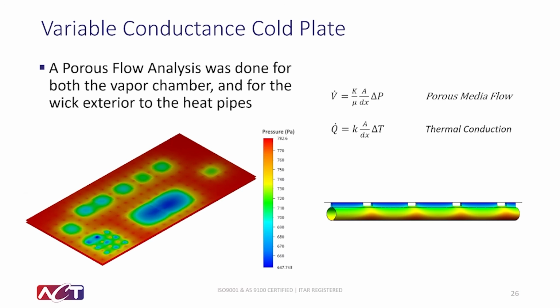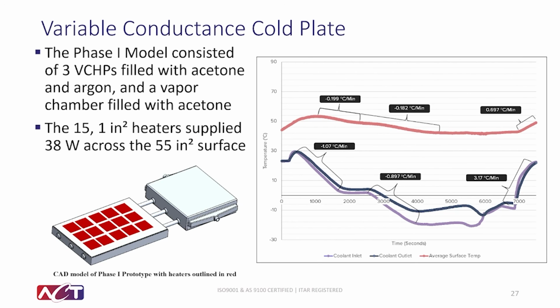Using the analytical model and the FEA thermal flow analogy, we designed a subscale prototype to use for testing. In phase 1, this prototype was fabricated out of aluminum alloy using direct metal laser sintering. The phase 1 model consisted of 3 VCHPs, and the cold plate was charged with acetone in the vapor chamber and acetone and argon in the VCHPs. A simple, single-phase pump loop was constructed for testing the variable conductance cold plate, and our test consisted of rapidly changing the coolant temperature and recording how the surface temperature of the VCCP changed.